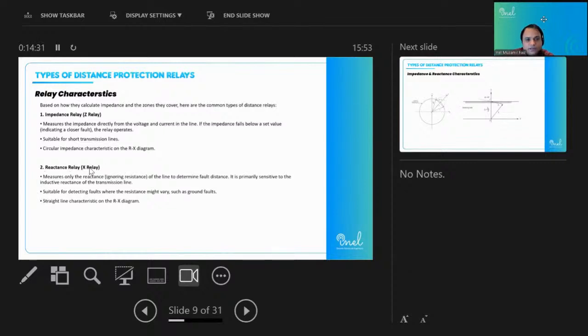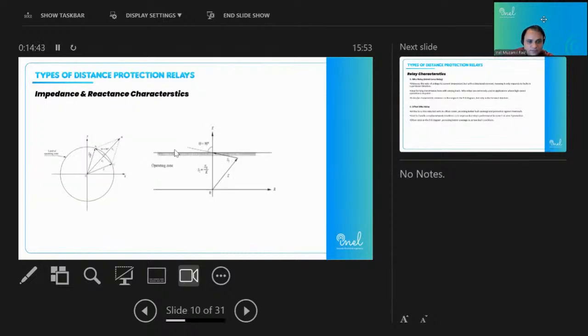The second option is the reactance relay. In the reactance relay, the value is increasing in the X direction. Like this is X. Now it is a constant on the Y-axis, but its X-axis is changing. This is typically preferred for those lines which are short in nature, because if the line is short, then its R value will also be small. And if the R value is small, then if an arc is produced during the fault, which I think everyone knows, when there is an energization or de-energization, there will be an arc produced, and that arc has a resistance value.